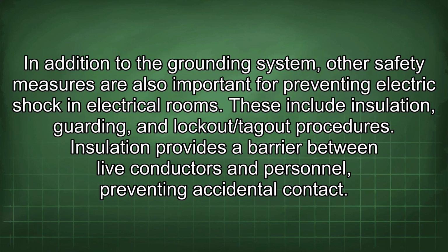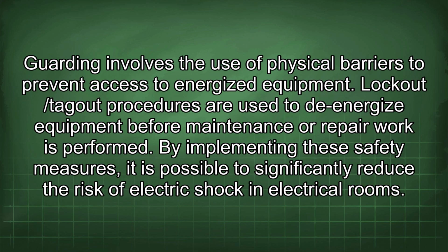In addition to the grounding system, other safety measures are also important for preventing electric shock in electrical rooms. These include insulation, guarding, and lockout/tagout procedures. Insulation provides a barrier between live conductors and personnel, preventing accidental contact. Guarding involves the use of physical barriers to prevent access to energized equipment. Lockout/tagout procedures are used to de-energize equipment before maintenance or repair work is performed. By implementing these safety measures, it is possible to significantly reduce the risk of electric shock in electrical rooms.